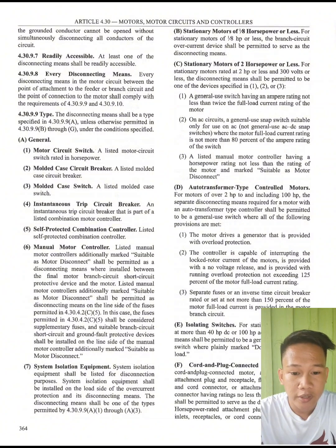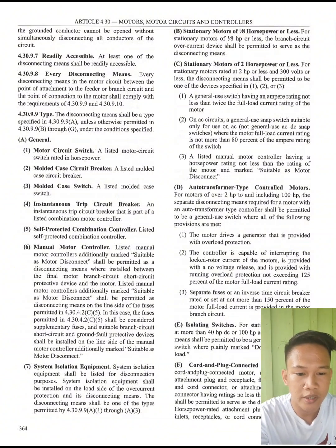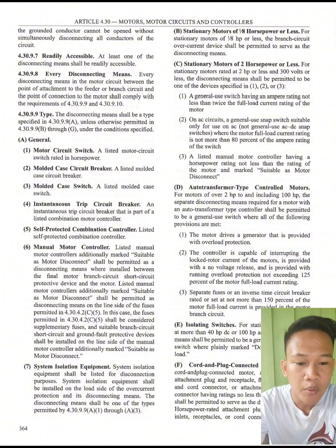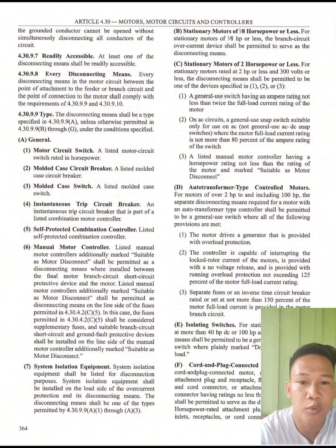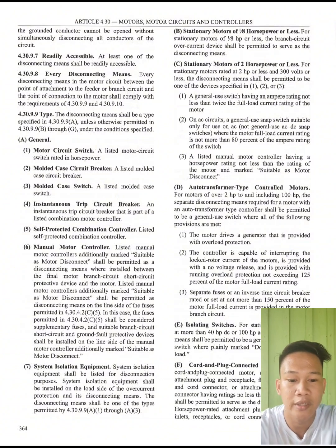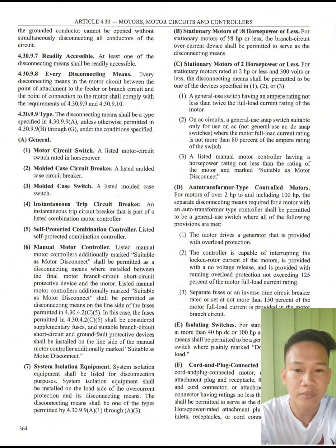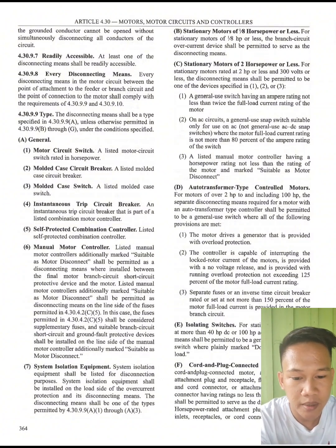Next is 4.30.9.8. Every disconnecting means in the motor circuit between the point of attachment to the feeder or branch circuit and the point of connection to the motor shall comply with the requirements of 4.30.9.9 and 4.30.9.10. 4.30.9.9 type. The disconnecting means shall be a type specified in 4.30.9.9a unless otherwise permitted in 4.30.9.9b through G under the conditions specified.